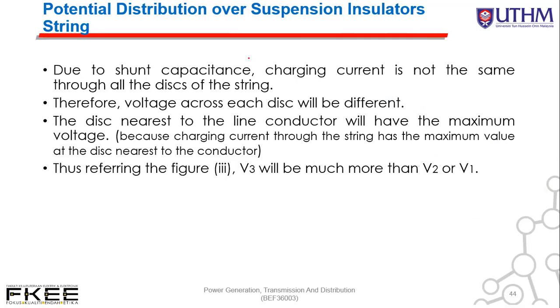Okay. Due to shunt capacitance, the charging current is not the same through all the discs of the string. Current dia adalah berbeza-beza. Therefore, the voltage across each disc will be different. Saya dah terangkan tadi. The disc nearest to the line conductor will have maximum voltage because the charging current through the string has the maximum value at the disc nearest to the conductor. Okay, refer to figure 3. V3 will be much more than V2 or V1.